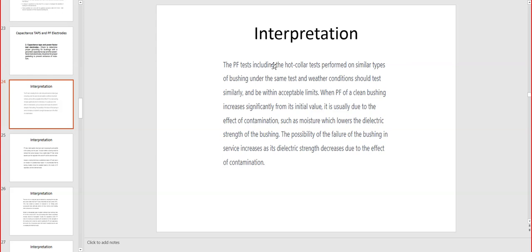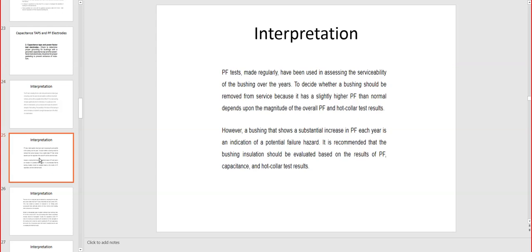Interpretation: power factor tests, including the hot collar test, performed on similar type of bushing, under similar weather and temperature conditions, should give you the same value. So when you measure the bushings on 3-phase high voltage, they should give you similar values, and if you do that on the low voltage, they should give you similar values. Even similar transformers should give you the same if the same manufacturer is used, the same manufacturer provides the bushings.